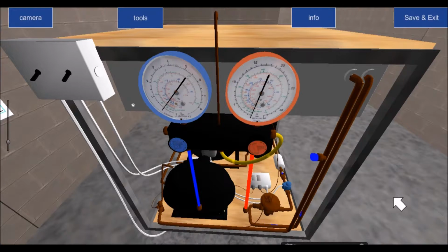So if you ever come across a system that has the operating characteristics of a system that is short of gas or undercharged, you must make sure first and foremost that the system is leak tight before you add refrigerant to it. It is illegal to assume that it has lost its gas charge because somebody was putting gauges on and off or because of human error. It is a legal requirement for any engineer to carry out a full and comprehensive leak test before they ever add refrigerant to a system that's running short.